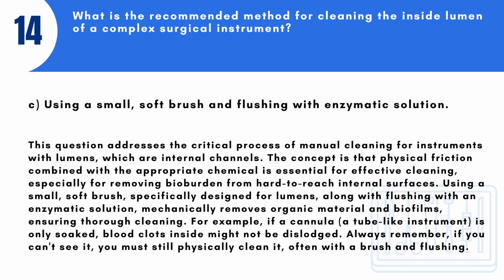Answer: C. Using a small, soft brush and flushing with enzymatic solution. This question addresses the critical process of manual cleaning for instruments with lumens, which are internal channels. The concept is that physical friction combined with the appropriate chemical is essential for effective cleaning, especially for removing bioburden from hard-to-reach internal surfaces. Using a small, soft brush, specifically designed for lumens, along with flushing with an enzymatic solution, mechanically removes organic material and biofilms, ensuring thorough cleaning.